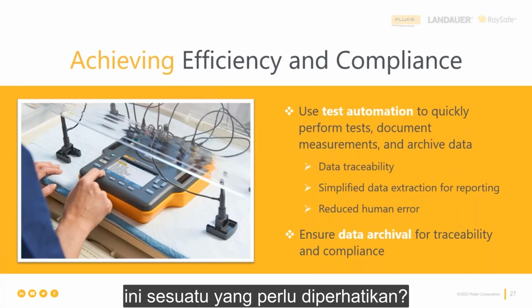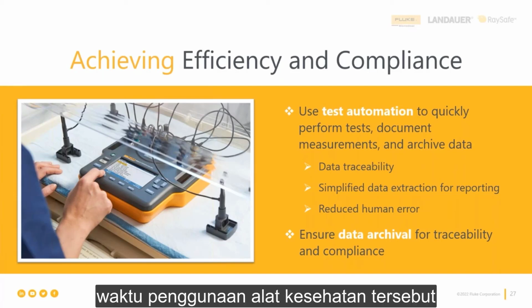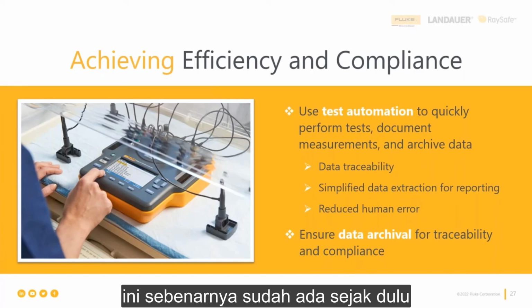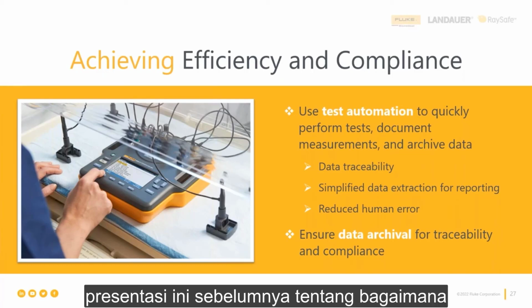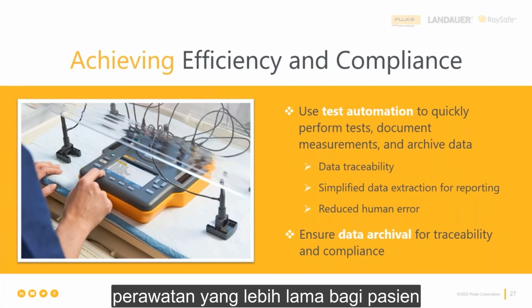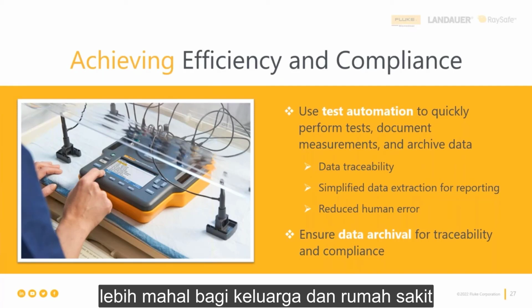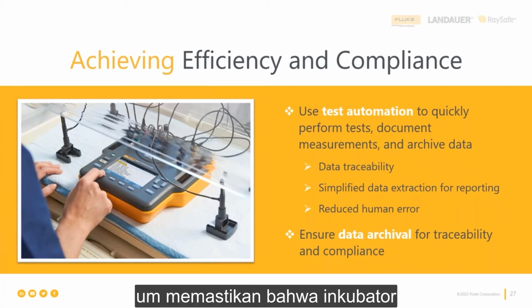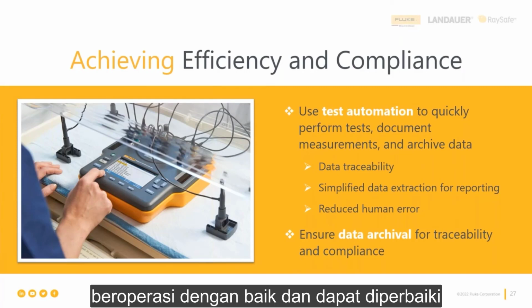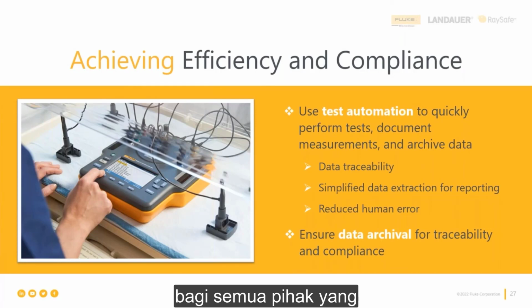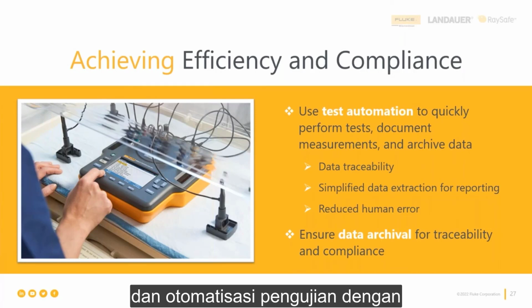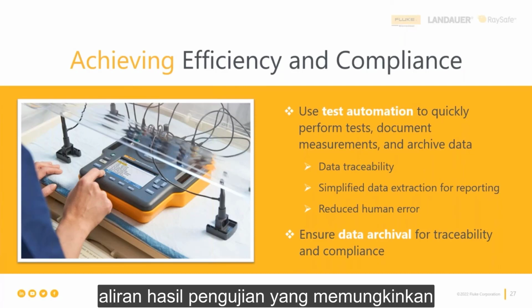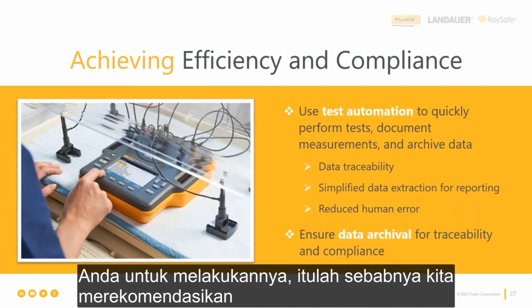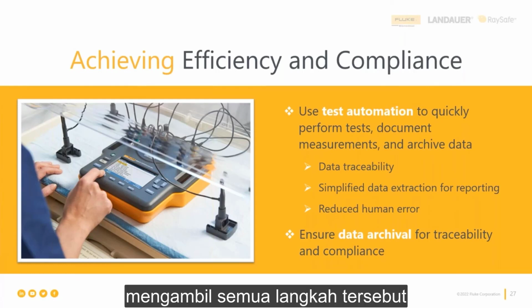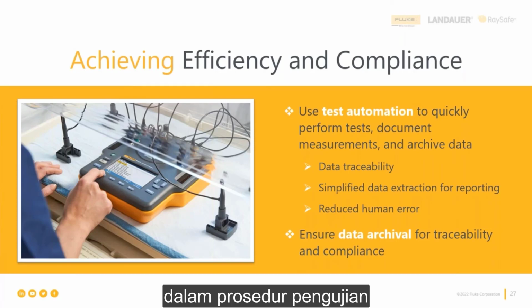Why is this something to pay attention to? Because it saves money for the facility and increases the amount of time that the medical device is available to use. This goes back to the point that Michael was making earlier in this presentation about how a longer stay for the patient is costly for both the family and the hospital. So ensuring that the incubator is operating properly and can be repaired in a timely fashion is extremely important for all of the parties involved. Test automation, with that continuous stream of test results allowing for predictive maintenance, makes this possible. That is why we recommend taking all of those steps in your test procedure for infant incubators.